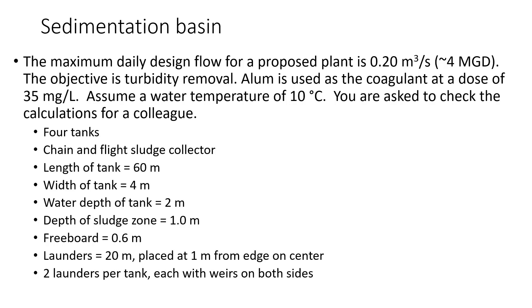We have a design flow of 0.2 meters cubed per second, about 4 MGD, and the objective is turbidity removal. Alum is used as the coagulant at a dose of 35 mg per liter. Assume a water temperature of 10 degrees C, and you're asked to check the calculations for a colleague. The flow is divided into four tanks. We're told there's a chain-and-flight sludge collector. We're given the length, width, water depth of the tank, sludge zone depth, freeboard, and information about the launders.